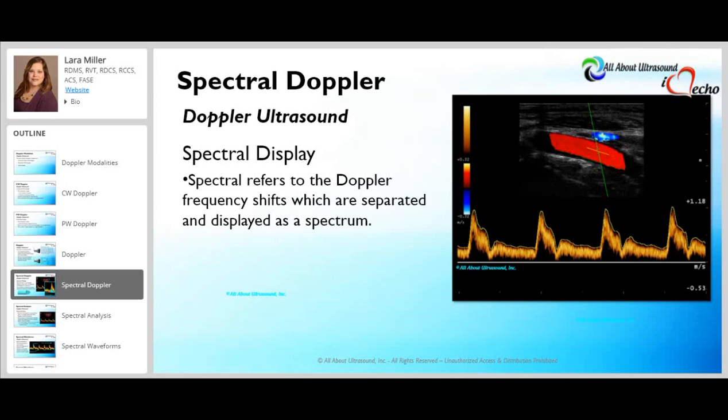The spectral display refers to the Doppler frequencies displayed as a spectrum — a waveform with velocity information versus time. The frequency shifts displayed are determined by all the factors associated with the Doppler equation, and higher velocities produce higher frequency shifts. The amplitude or strength of the echoes displayed in the waveform is determined by parameters that affect power, such as the type and amount of reflection and the attenuation of the sound beam.